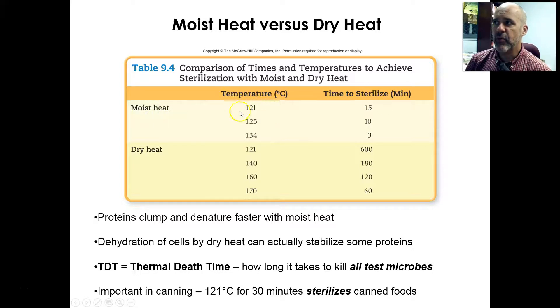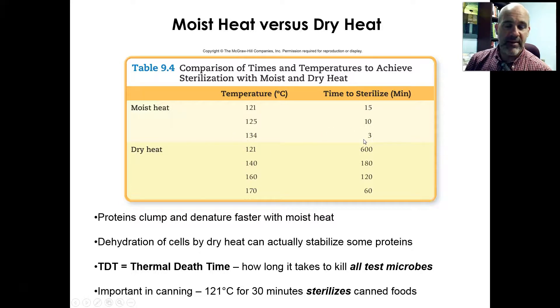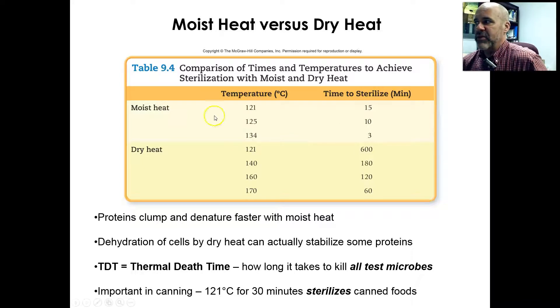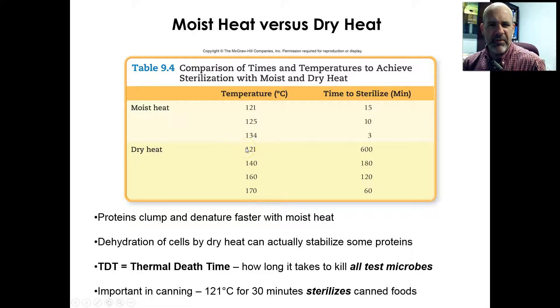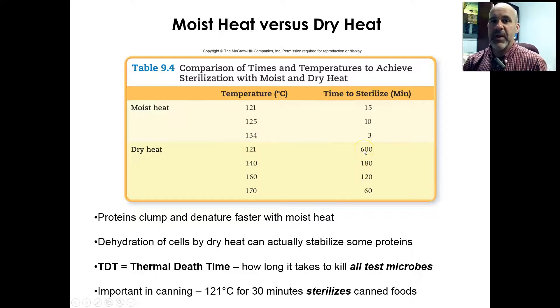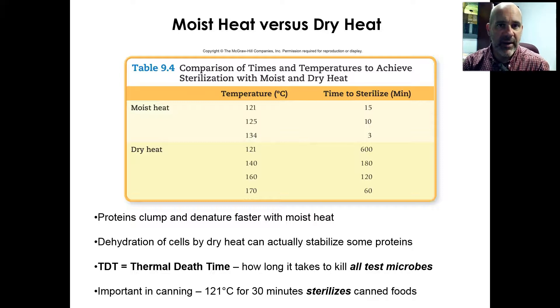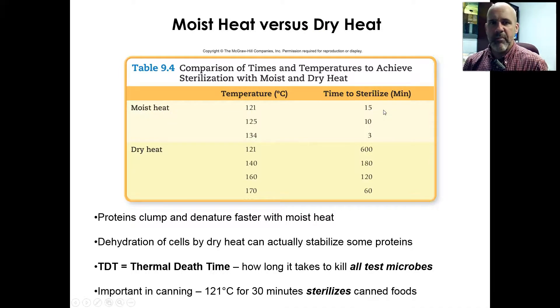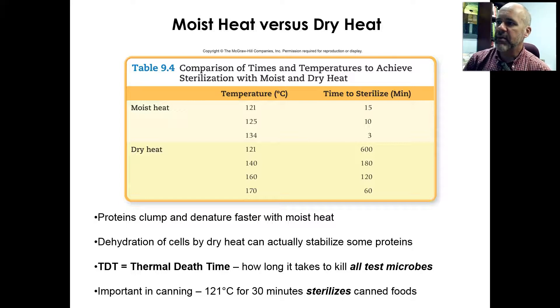Moist heat at 121°C takes about 15 minutes to sterilize, and if you go up to 134°C you're down to only 3 minutes necessary to achieve sterilization. But look at dry heat: 121 degrees Celsius dry heat — that's about 256°F — would take 600 minutes, or 10 hours. So if you put something in an oven at about 250°F, it's going to take 10 hours before you can feel confident that whatever you put in there was completely sterilized. Moist heat only needs 15 minutes, so it's a huge difference. That moisture plays a huge role in how quickly hot temperatures get transferred into a substance.